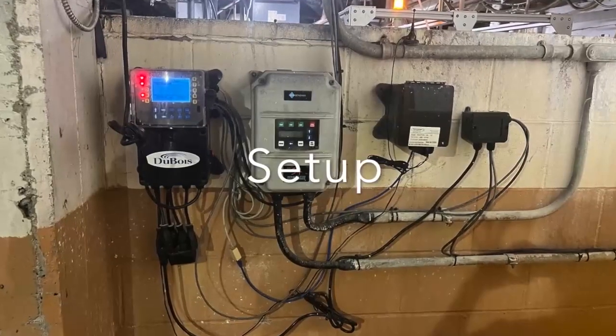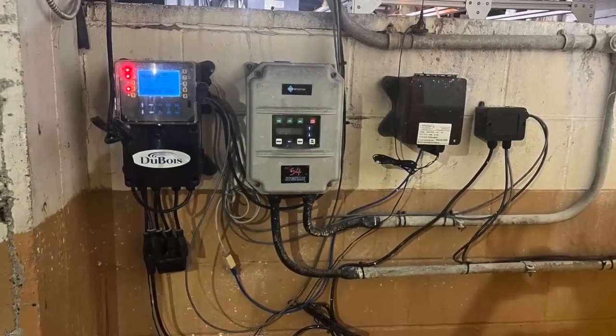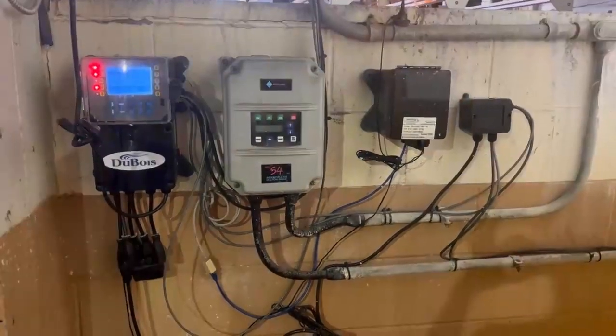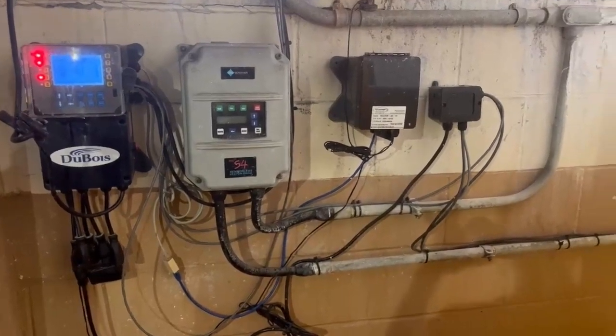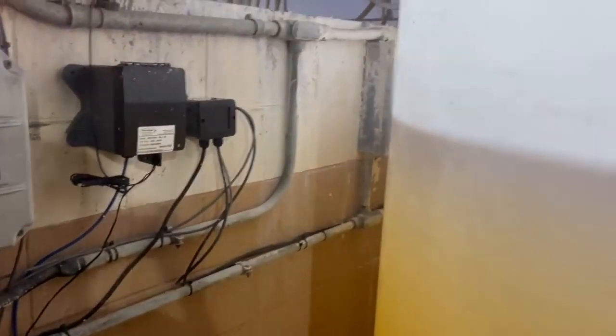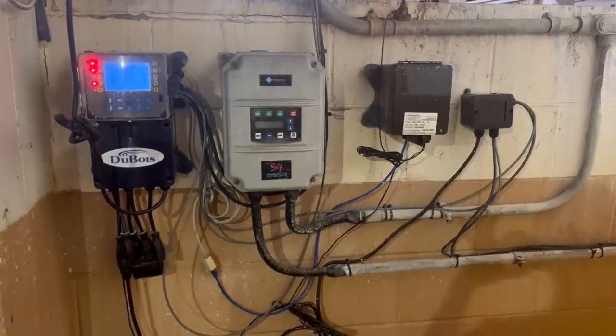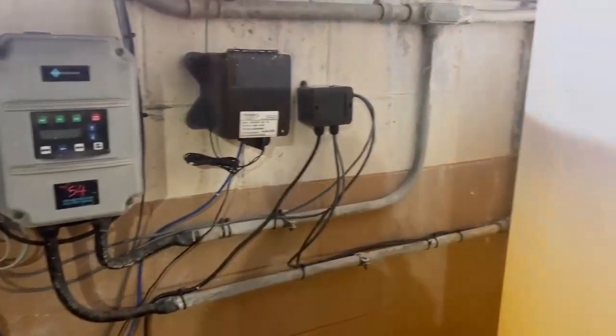Setup. Fasten the monitor, router, and converter to the wall before you begin wiring. Make sure the monitor is near a power source. You also want to make sure the converter is close enough to where the tank is so it can be wired together using the wire attached to the probe. Your probe should also not be more than 200 feet away from your router.